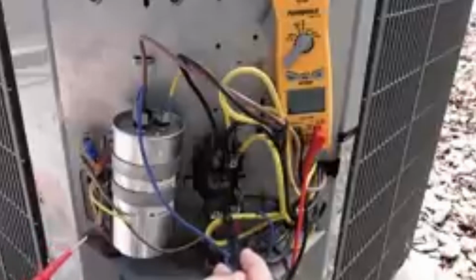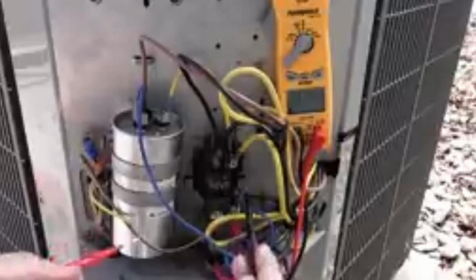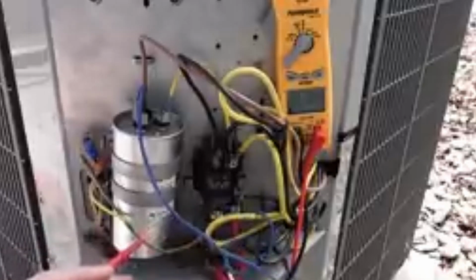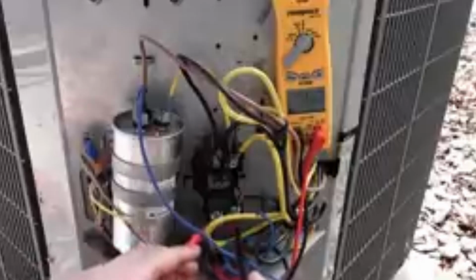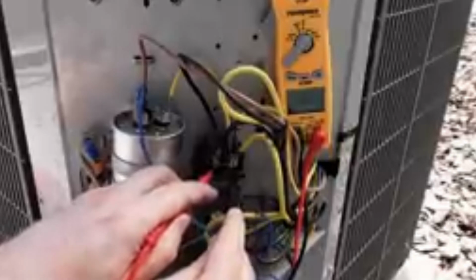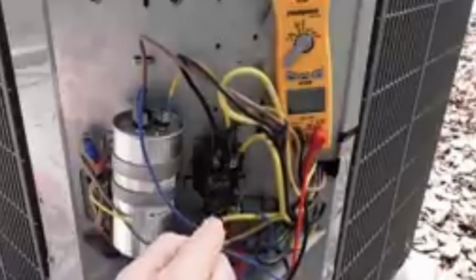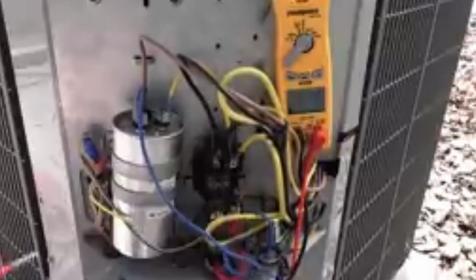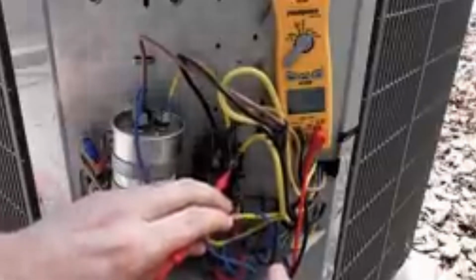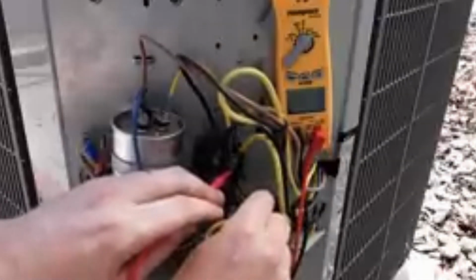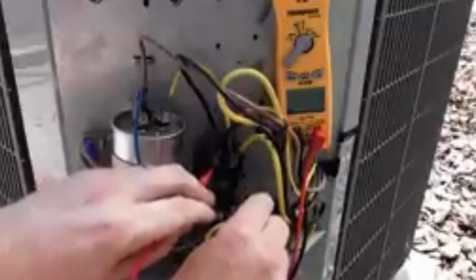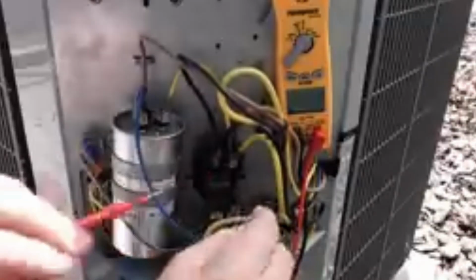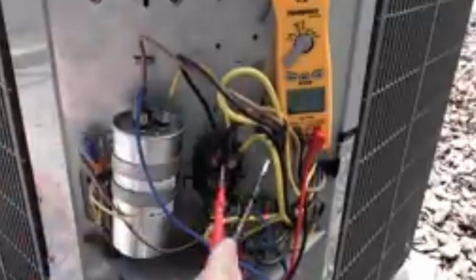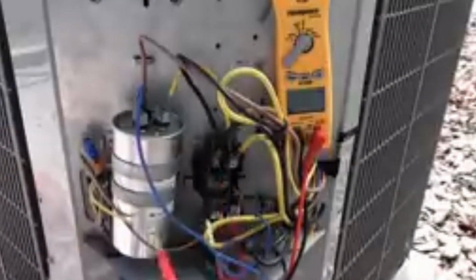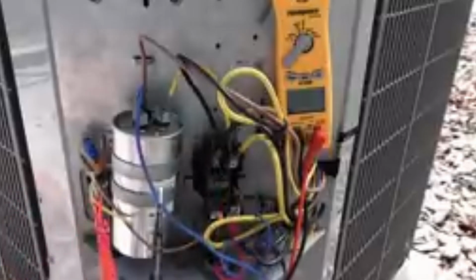Now our contactor coil is pulled out. You can see this position is now further out because the electromagnet's released because I've unhooked the 24 volts. So now coming into the contactor, we have 214 volts, and coming out now we read nothing because there's an open path, because this is no longer allowing any potential through the contacts. But this is still not a safe circuit, because if I measure from here, you'll see I still have 123 volts. And even on the other side, I show 123 volts because it backfeeds through the compressor back to this point. So a safety check is always to ground to ensure that you don't have any potential.